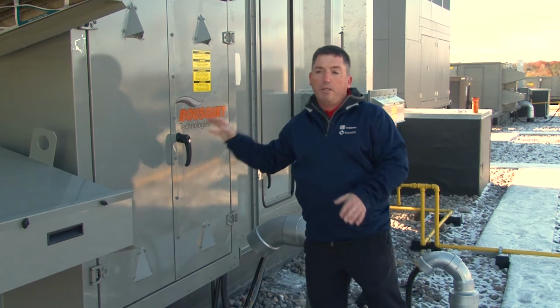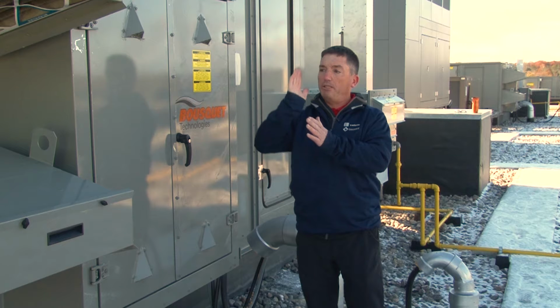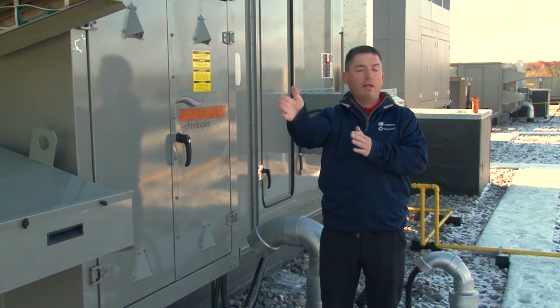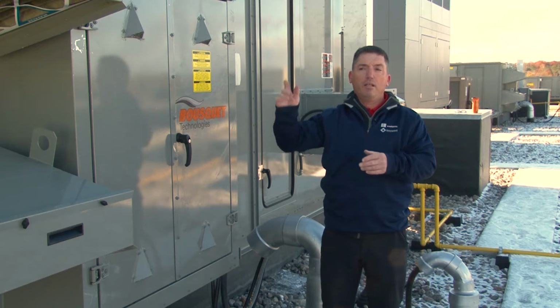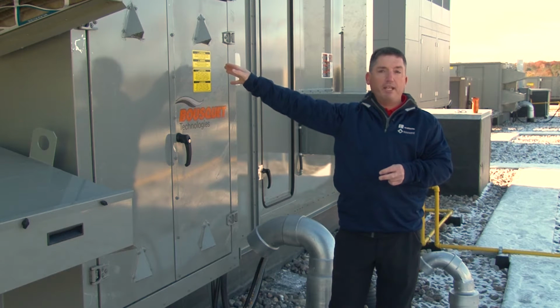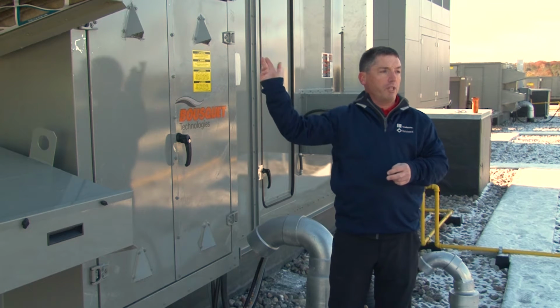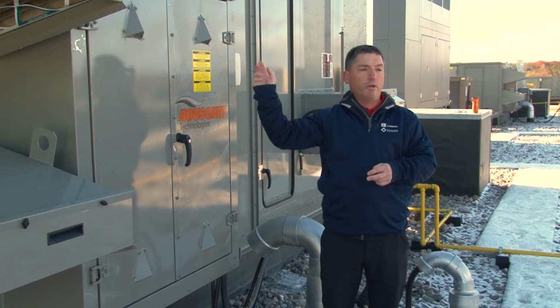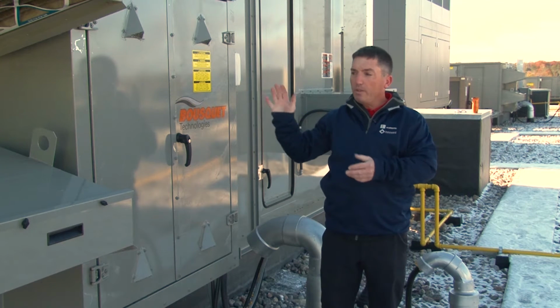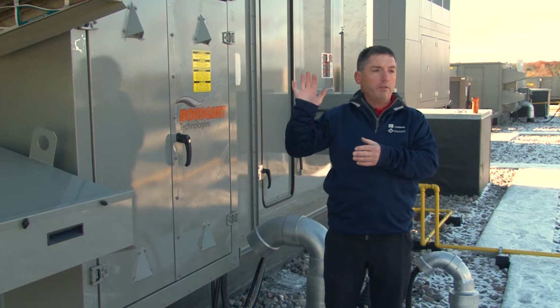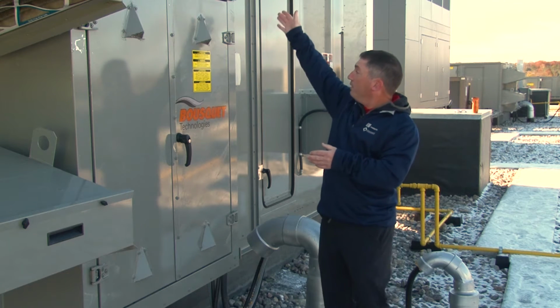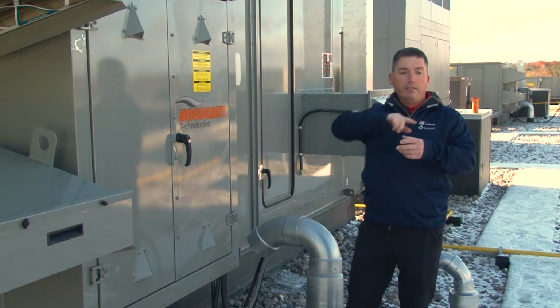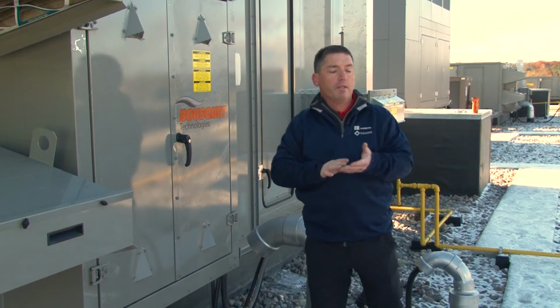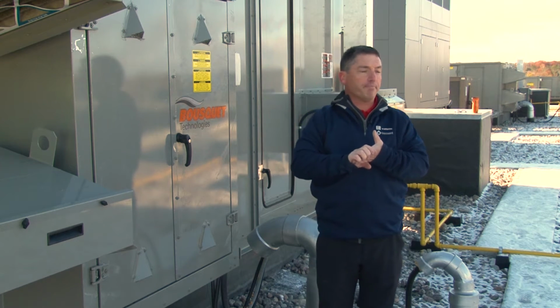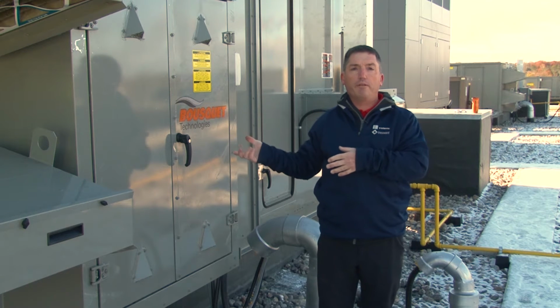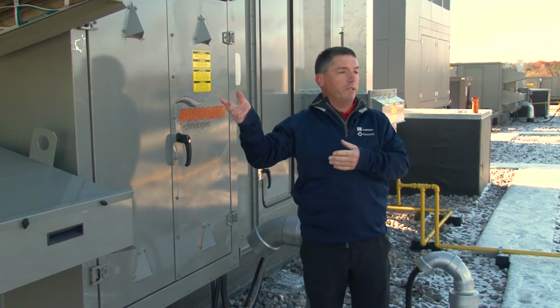So basically, think of the unit as split right down the middle along its length. On the opposite side from where I'm standing, that is where all of the exhaust air is going to be drawn from inside the building. It's drawn up through the bank of filters, and then right about this point there is an energy wheel that rotates. The principle is, in the winter time, we are exhausting warm air from the space. We're bringing in cold outside air.